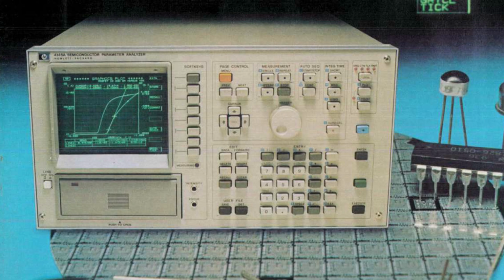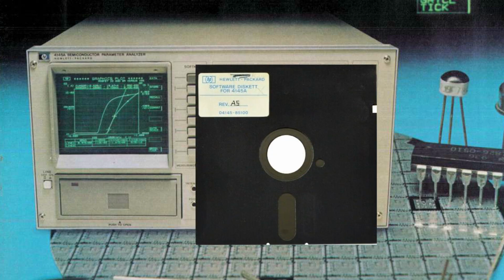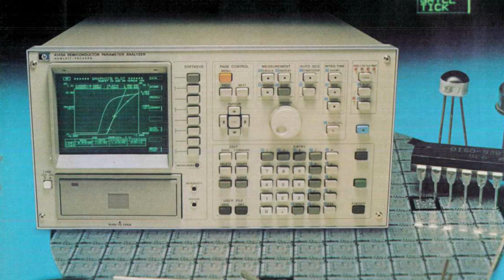Since the 4145A requires the system software to be loaded from the floppy drive, the system is unable to fully boot up. This unit was built in 1985. Like many of these machines, the system software floppy disk has degraded to the point where it is unable to be read. We must consider swapping out the floppy disk drive, and replace it with a more reliable modern form of media such as an SD card. Before we decide on a suitable replacement for the floppy drive, let's take a look at the drive currently installed.